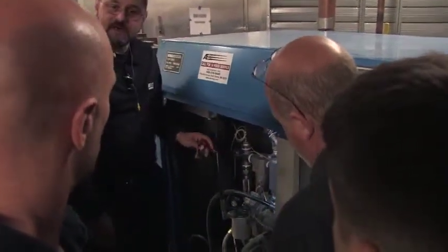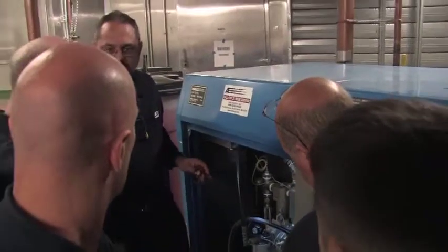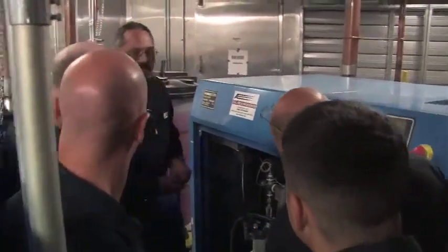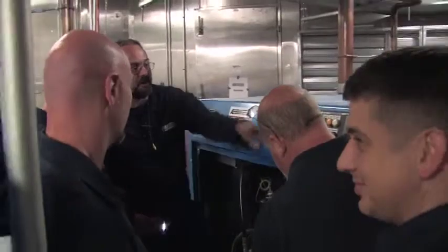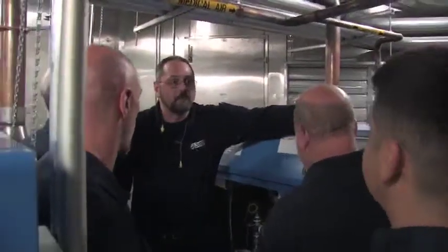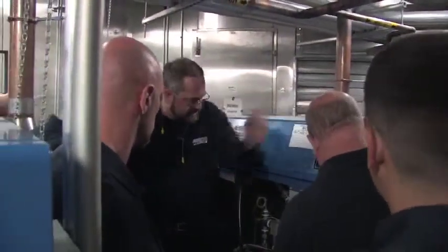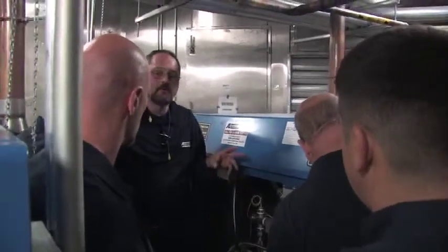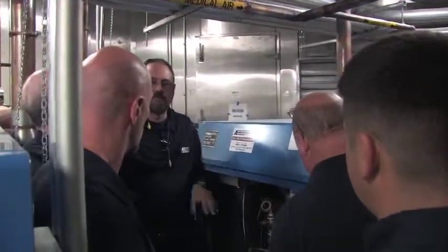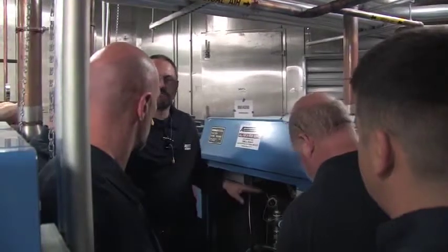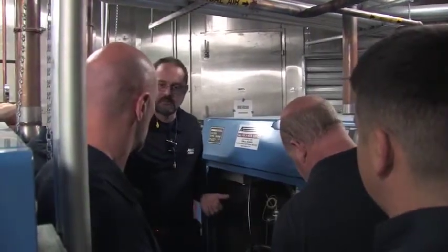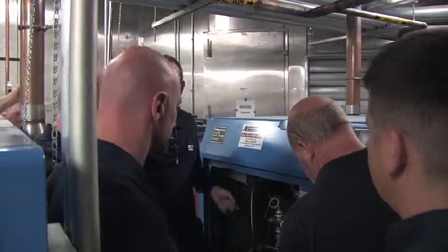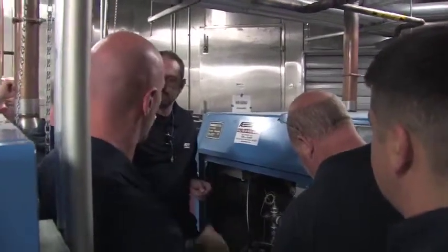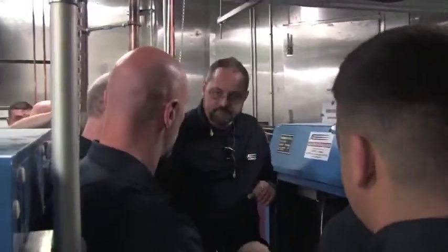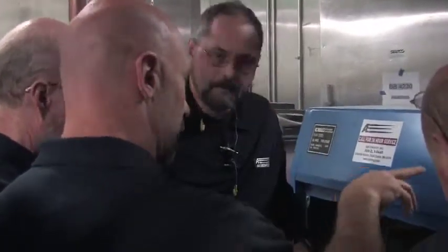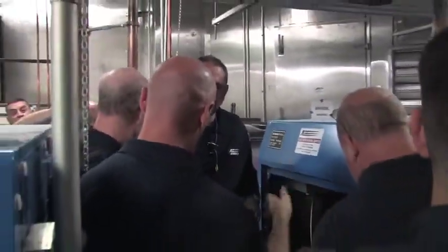The one thing they never ever want you to do on these machines is run them dry. That's why, for example, when we hit the start button, the first thing that starts is the oil pump. And when it sees enough pressure, then it starts the main drive. When we hit stop, the main drive shuts off. The air ends start coasting to a stop. The oil pump keeps running another 10 or 20 seconds until it coasts to a stop. That's because when we do our annuals and drain the oil out, when you go to start it back up, there's not enough oil in the system yet.